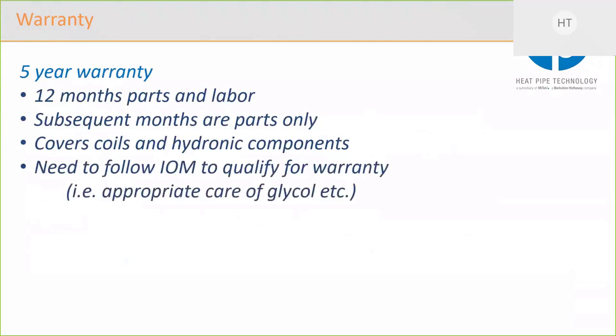One caveat is that you do need to follow the IOM to qualify for the warranty. An obvious example of that is appropriate care of the glycol. If the system gets charged with straight water and no inhibitor or no glycol, and that causes a problem downstream, like for example in winter, then that would obviously be an issue regarding the warranty. However, they're all sensible steps that need to be followed.